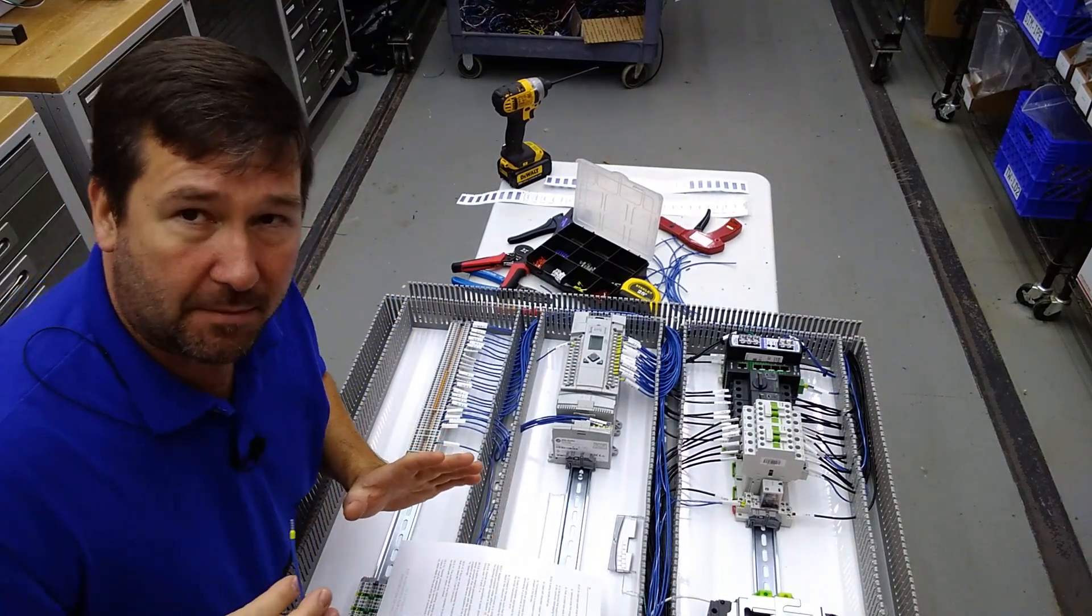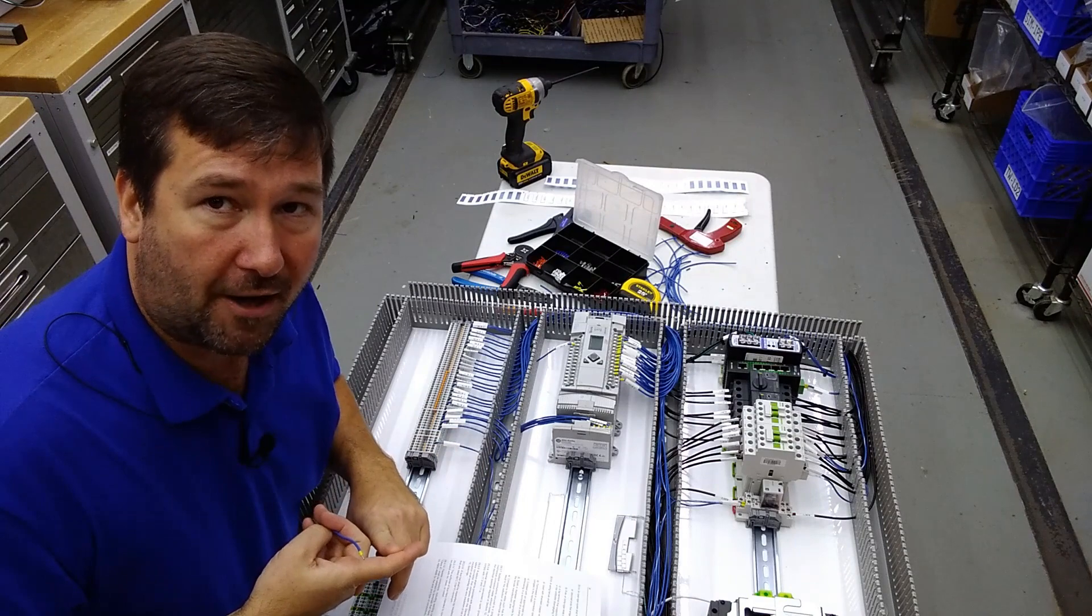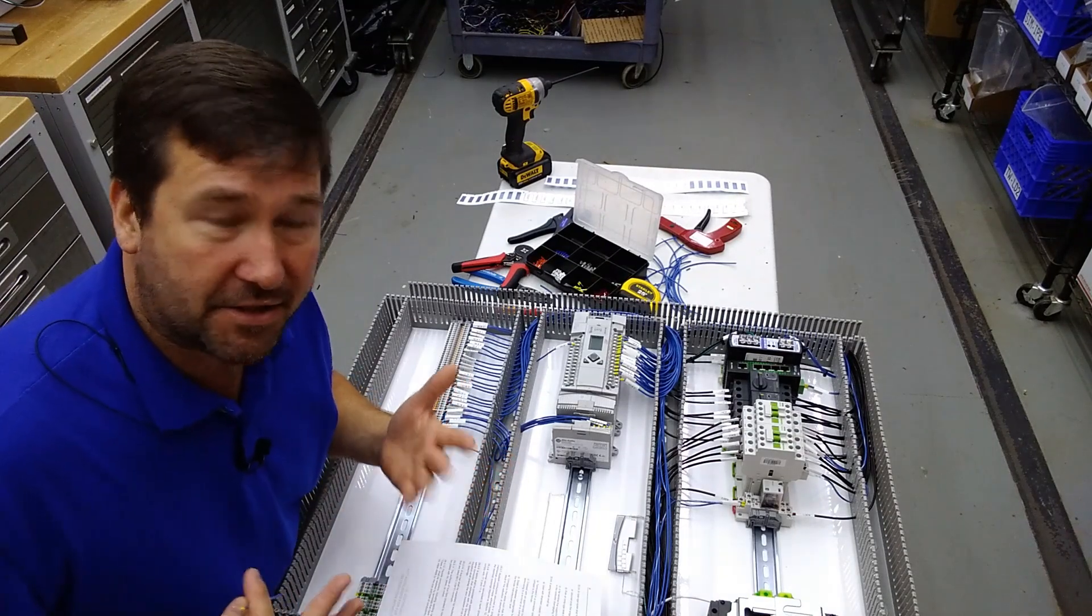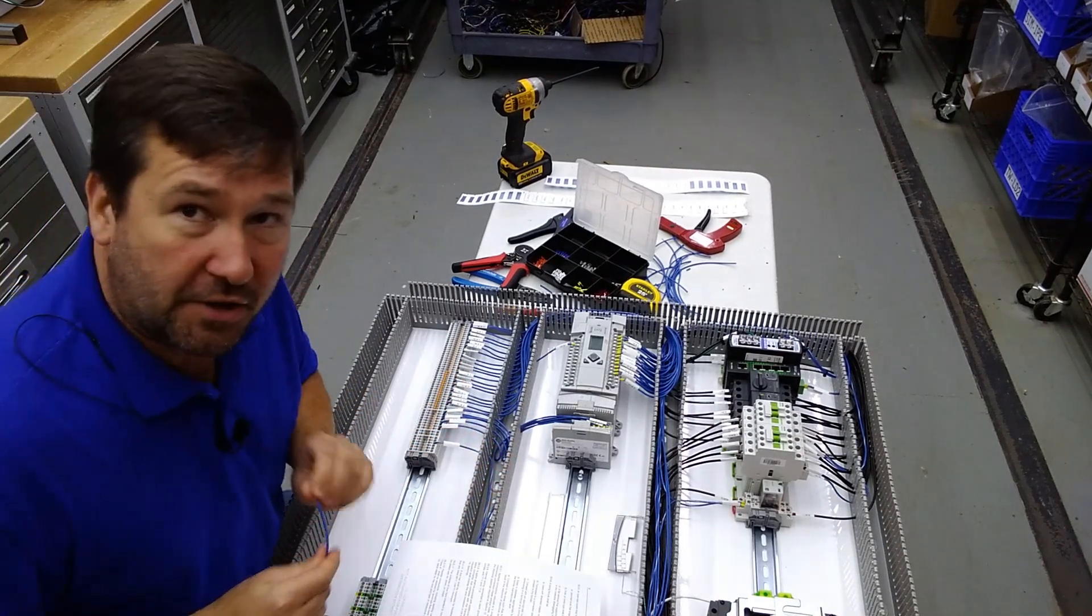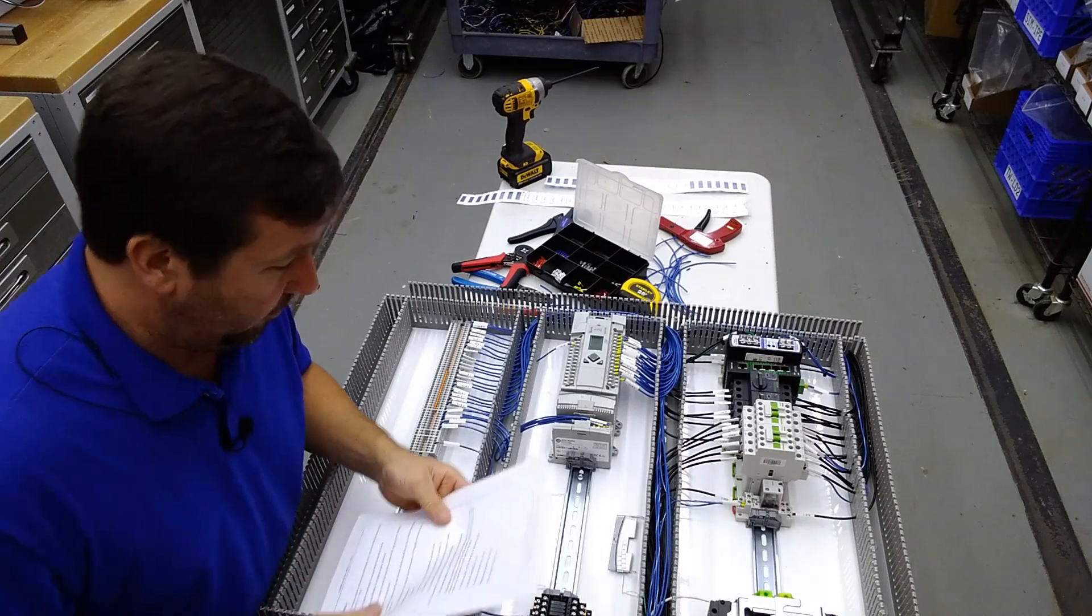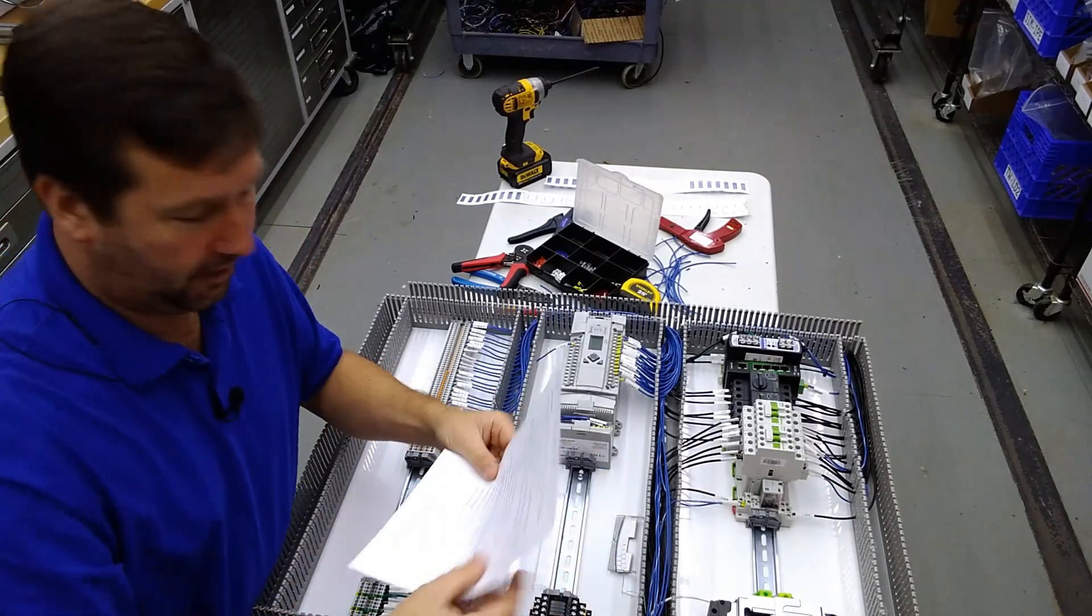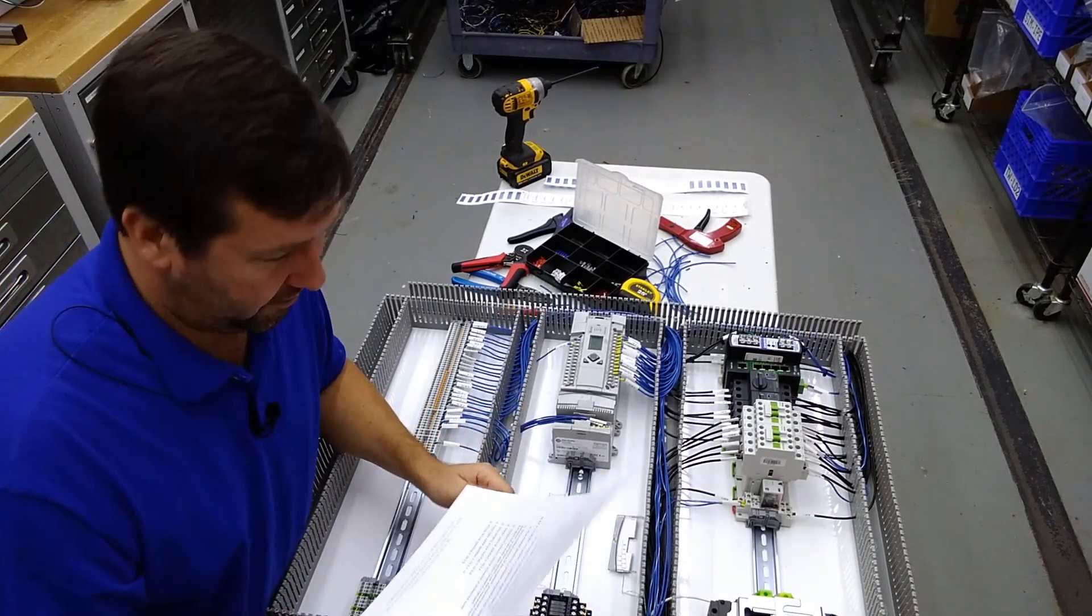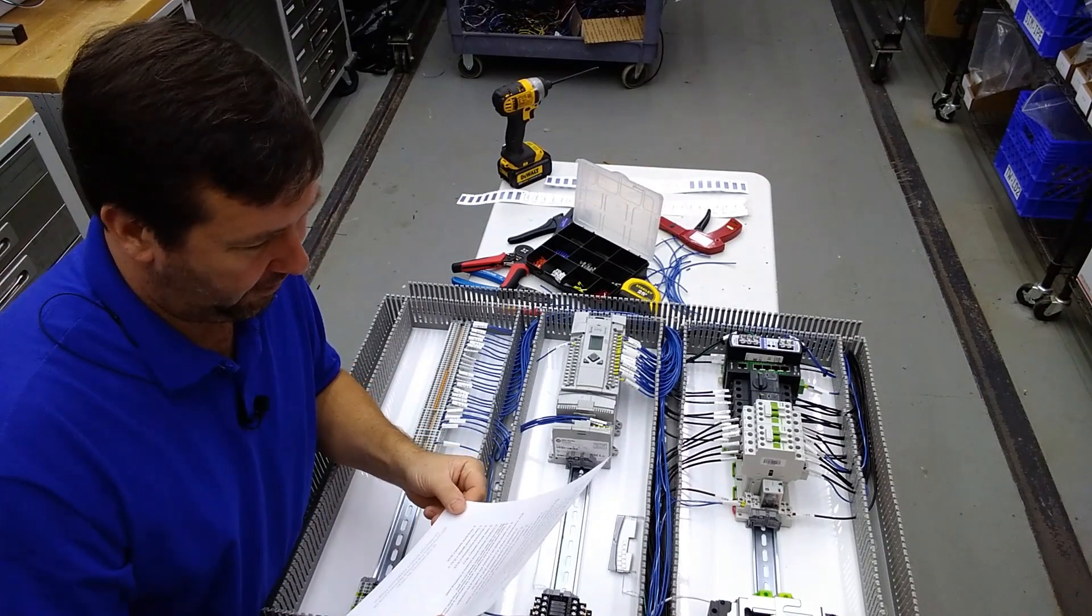So the main question that's come up is: are ferrules required and is there any disadvantage to using ferrules? Ferrules are not required, at least according to UL. So I went ahead and printed out UL because I'm not real familiar with this one, so I will have to read this one off.